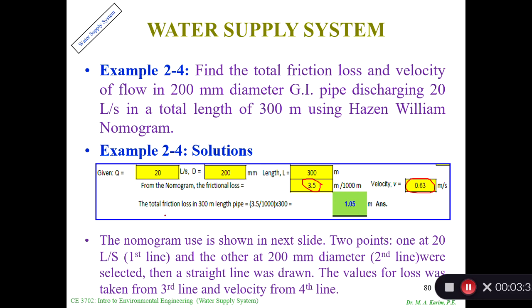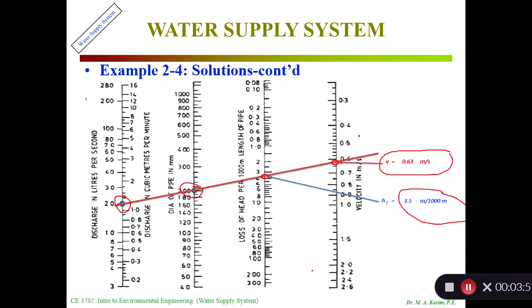Then I calculated this one. Total friction loss in 300 meter pipe length equals: this is 3.5 per 1000 meters, so how much would be in 300 meters? This divided by 1000 times 300 would be 1.05 meters. This is my head loss for the 300 meter pipe system. Here are the explanations.